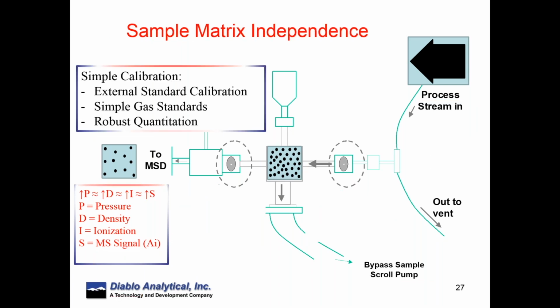So we can then use a simple external standard calibration because of the matrix independence capability of this. Simple gas standards in, say, helium, but then do a robust quantitation so that we can look at the components that are in our process stream.